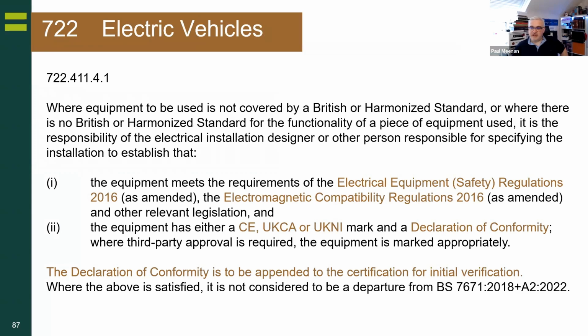One of the interesting bits, we obviously had Amendment 1, which pretty much rewrote and brought this 722 to us. There's a section 722.411.4.1 where equipment is to be used not covered by a British or harmonised standard. There is obviously a risk that we're not complying with low voltage directives or supply of electrical equipment regulations. So it's the responsibility of the electrical installation designer or person responsible for specifying the installation to establish the equipment meets the requirements of the electrical equipment safety regulations and the EMC regulations.